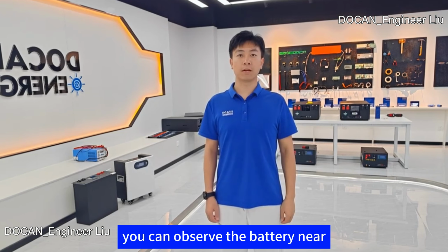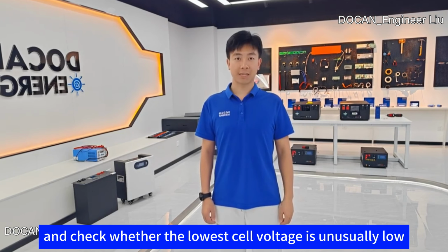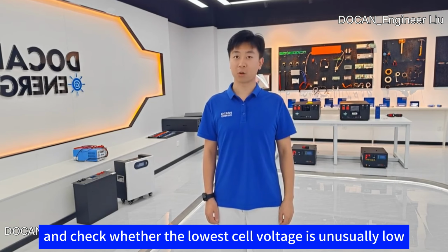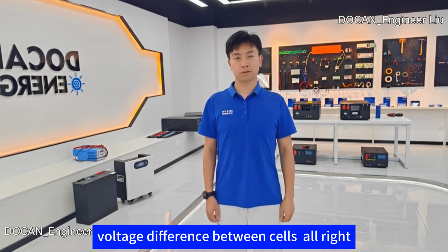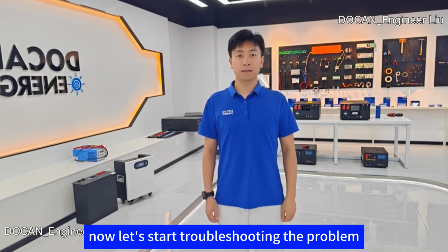The same principle applies to discharge testing. You can observe the battery near the discharge cutoff point and check whether the lowest cell voltage is unusually low or whether there is a large voltage difference between cells. All right, now let's start troubleshooting the problem.